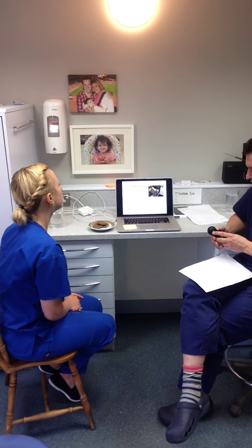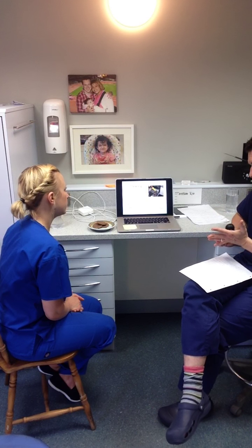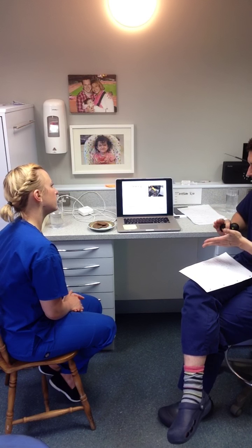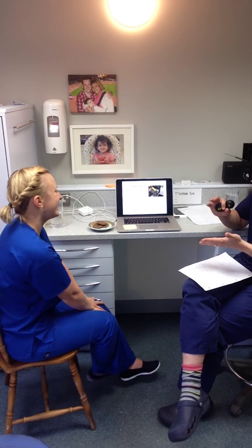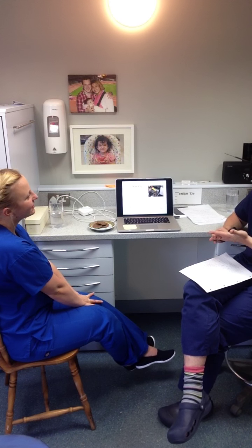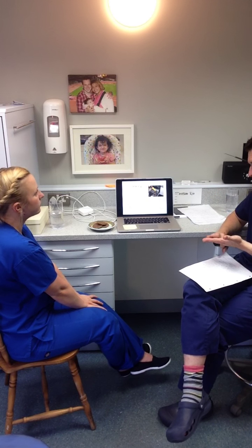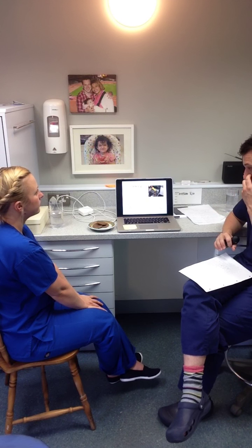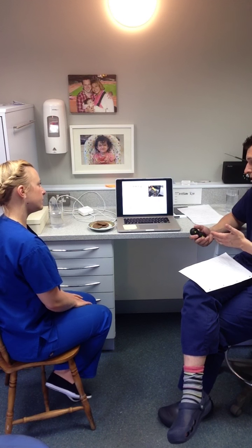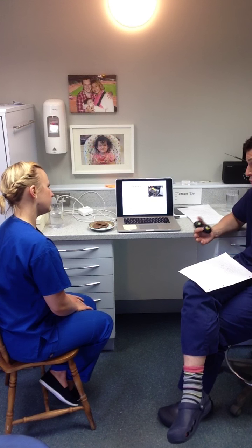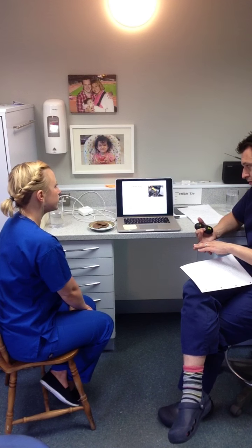So cleaning, I think I talk about 3 different stages. So there's cleaning with a washer disinfector, which is best practice, cleaning with an ultrasonic bath, and also manual cleaning. So one's more effective than another. So washer disinfector is best practice. So using a validated washer disinfector, it's good because it gives you validation that that washing phase has been successful, that the temperature has been maintained, and that it's gone through a whole cycle.